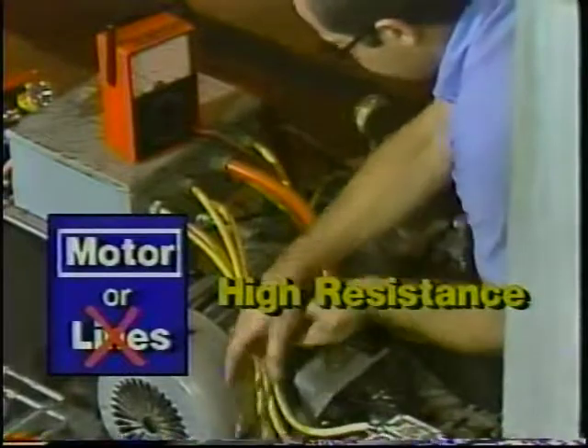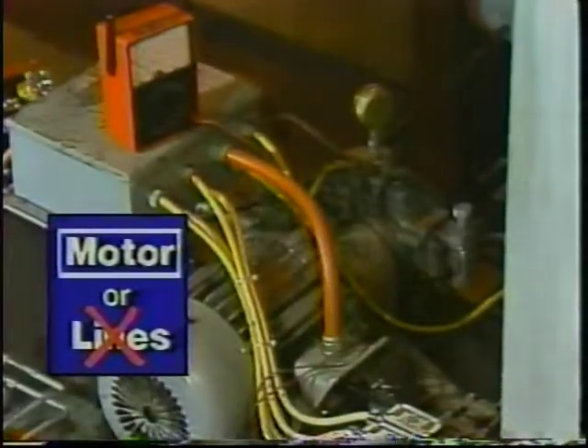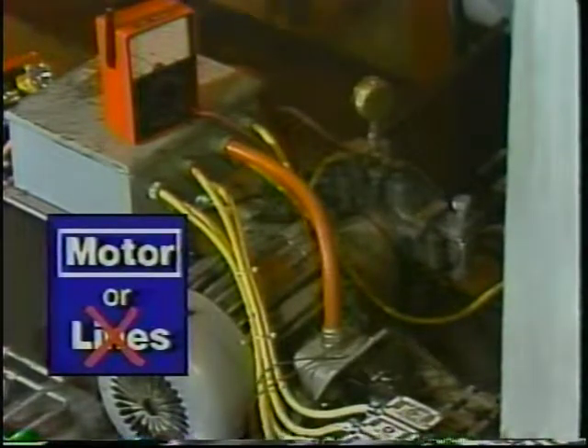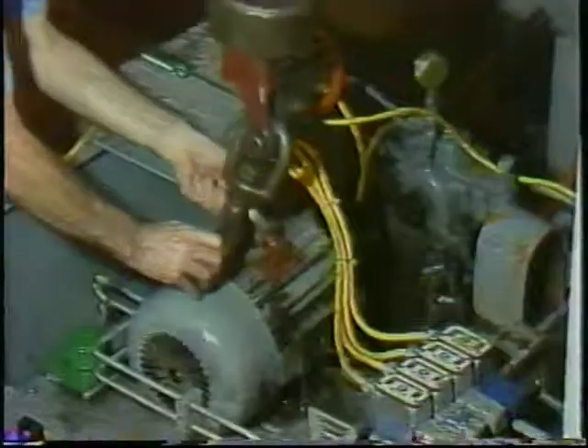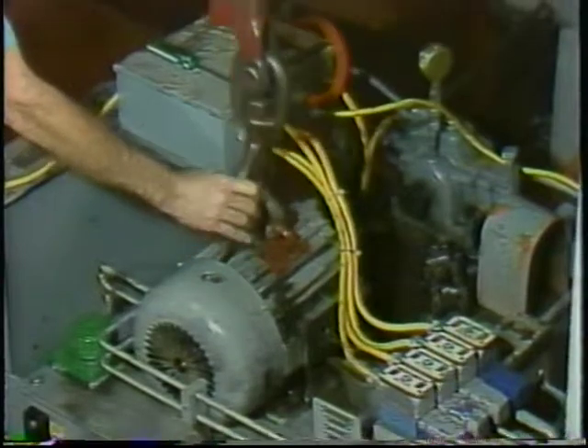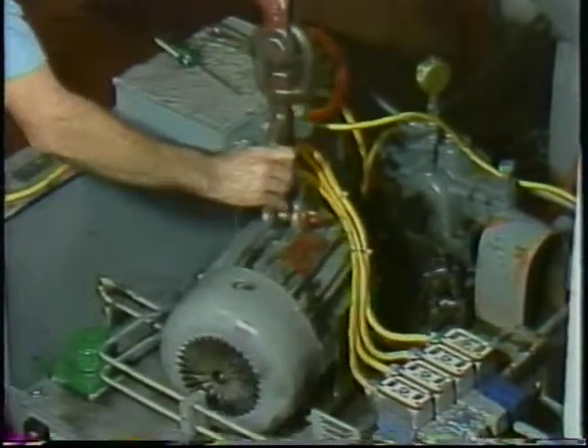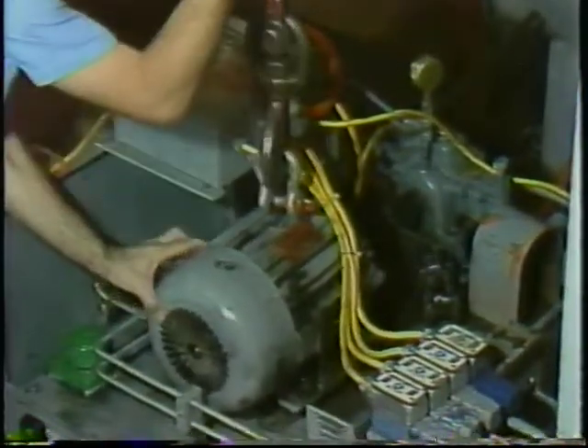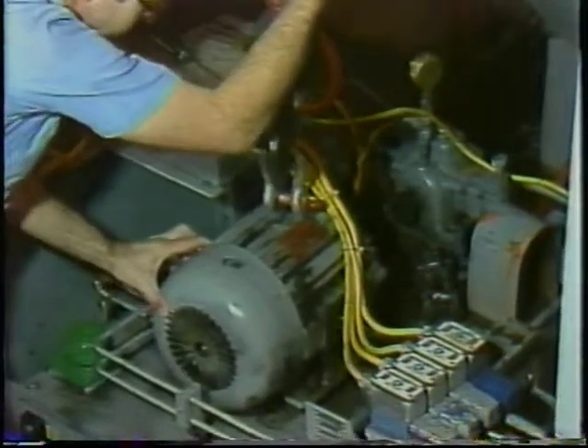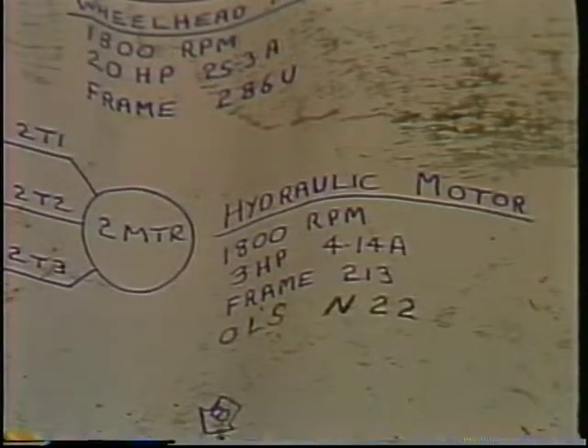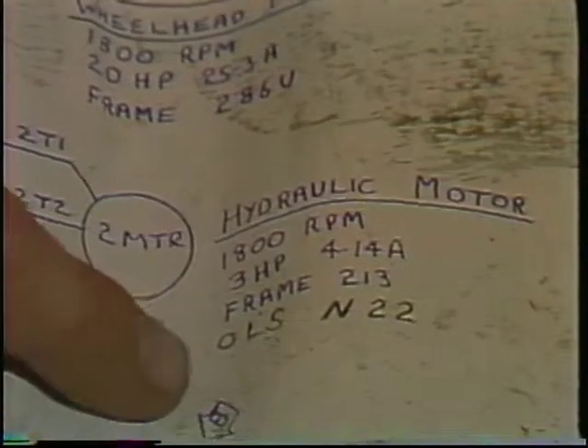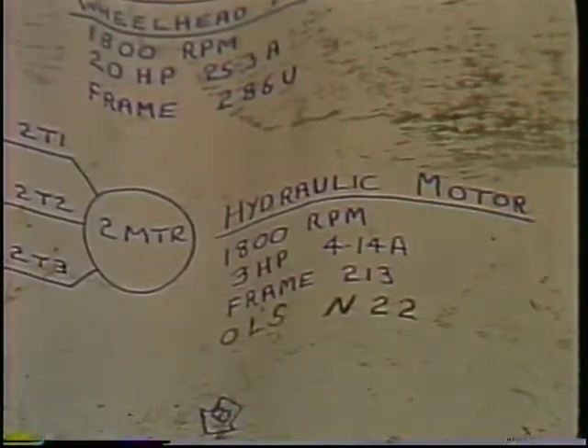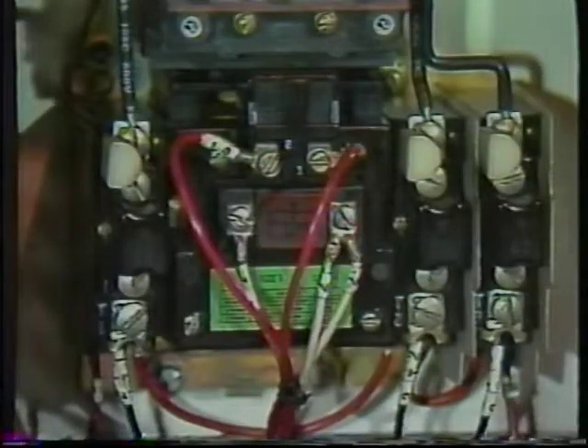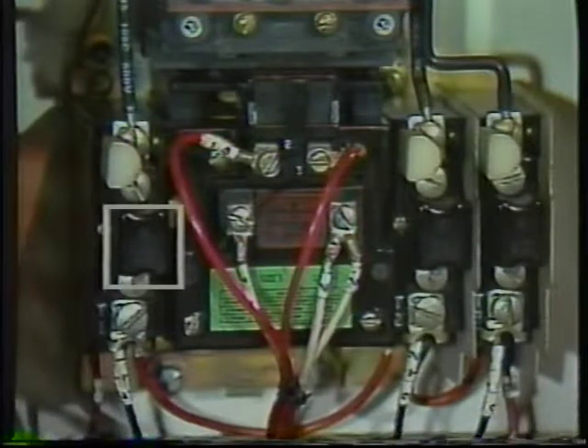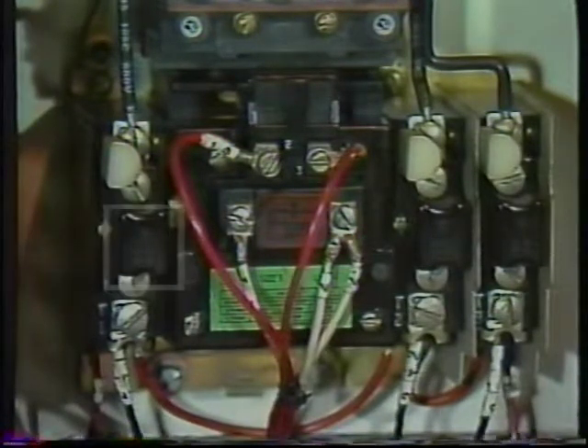The troubleshooting method has led you quickly and directly to the actual cause of the problem with a few simple tests to eliminate probable causes. Now don't forget that good troubleshooting also involves determining root causes. Before you connect up a new motor, you should try to determine why the old one burned out. Check the setting of the overload breakers. They are supposed to prevent motor burnout. Make sure nobody has tampered with them and that they are properly calibrated to protect the new motor.